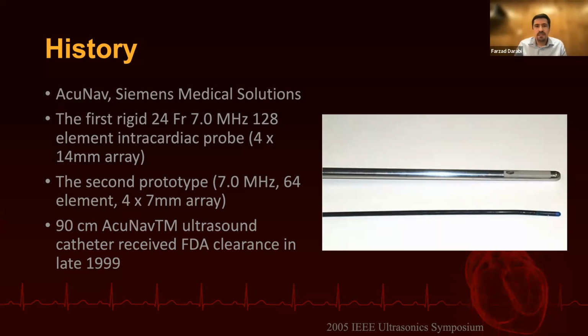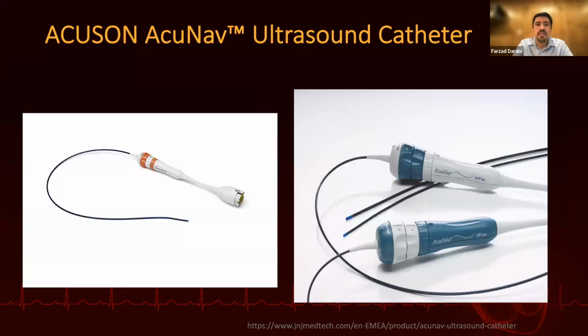With improvement of technology, now we have, to the best of my knowledge, 4 different companies making ICE probes. One of them is AcuNav, which is now owned by J&J. They have 3 different probes, 8 French and 9 French, which are 2D probes, and also the new 3D probe that can do 3D imaging of the ICE. It's basically a 64-element transducer. Their frequency is between 5 and 10, and their tissue penetration reaches about 15 centimeters.